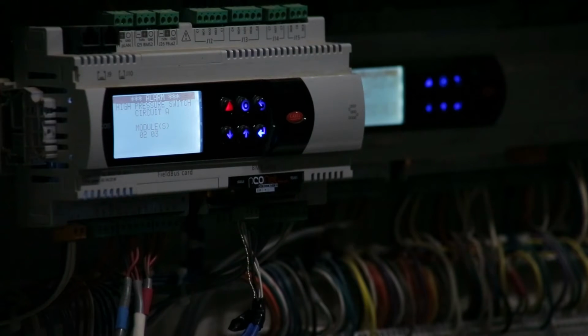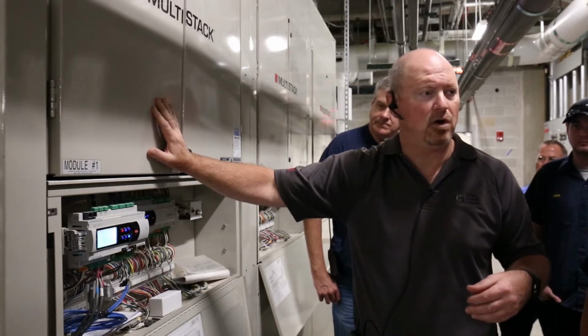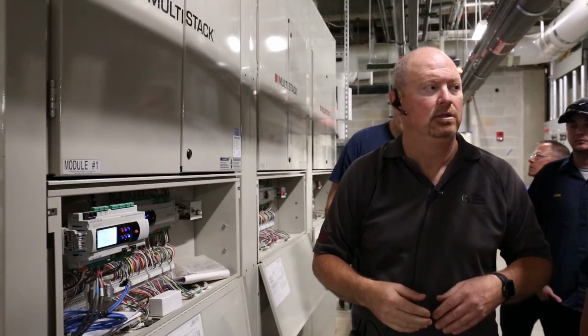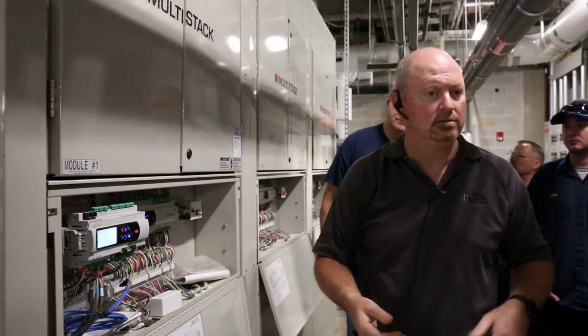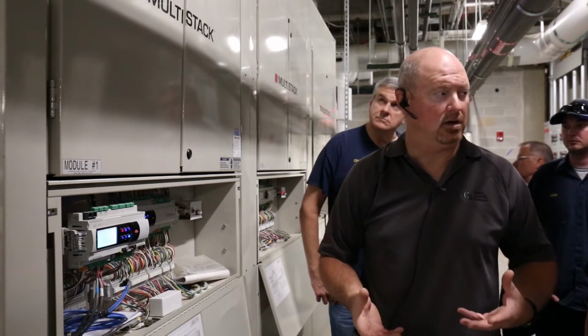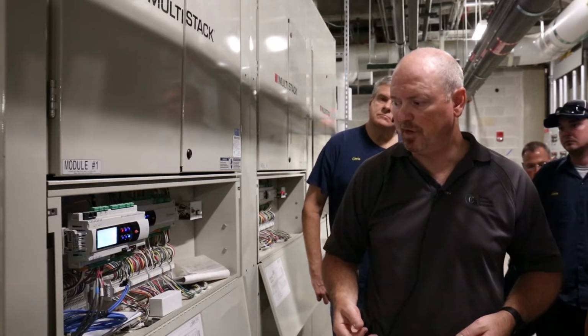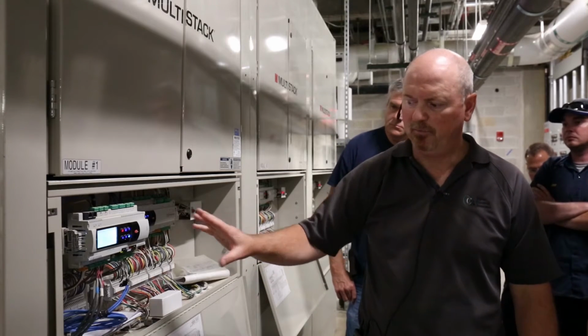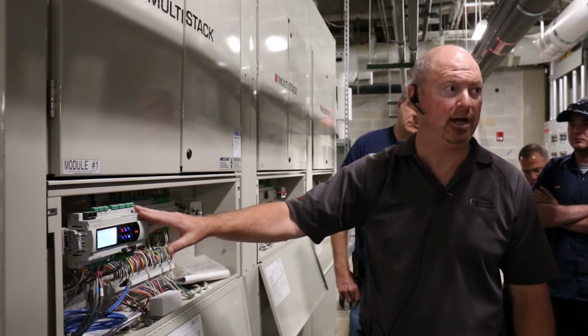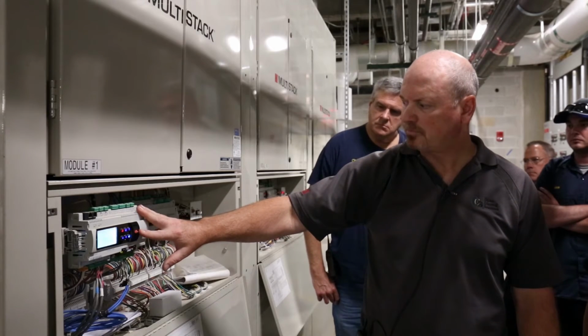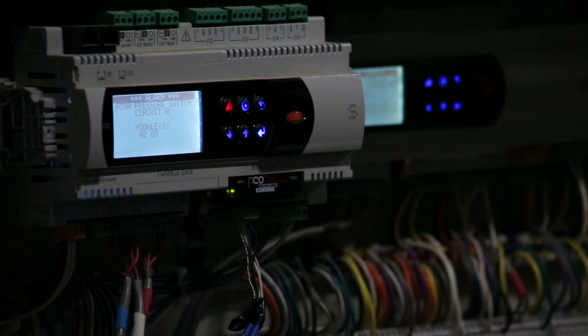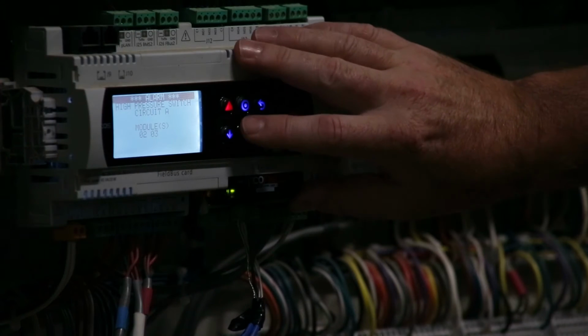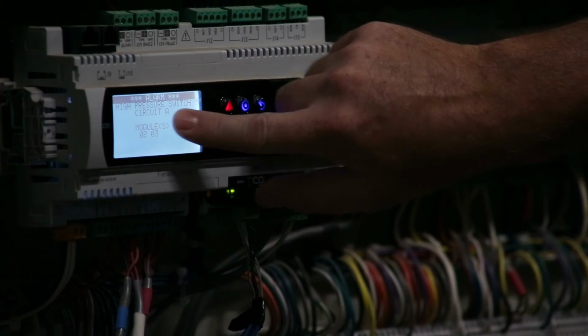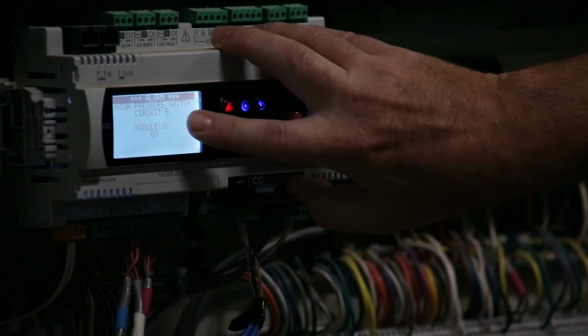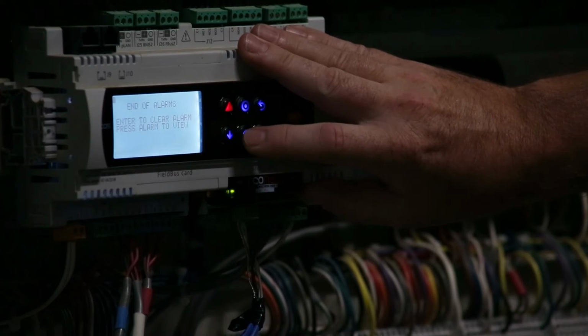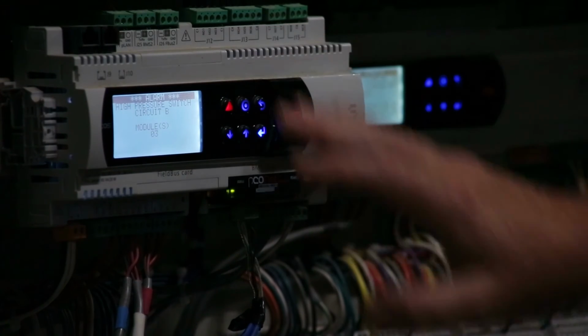This chiller is kind of like most chillers as far as refrigerant flow goes. It's water cooled on both sides. Your metering device is an electronic expansion valve, which is very accurate on these. I'm impressed. So as far as the high pressure switch, we'll have to get into a module here and find out which one it is. Circuit A, Circuit B, both. Looks like the first two modules have tripped on high head pressure.